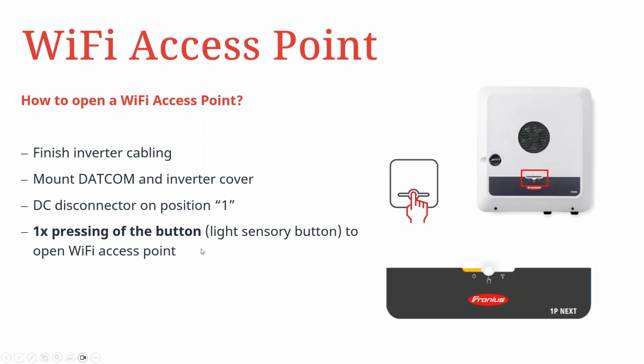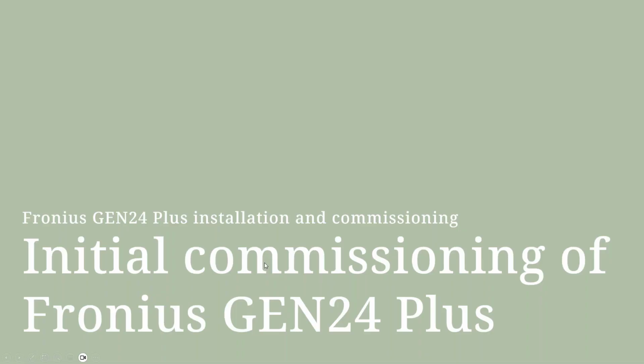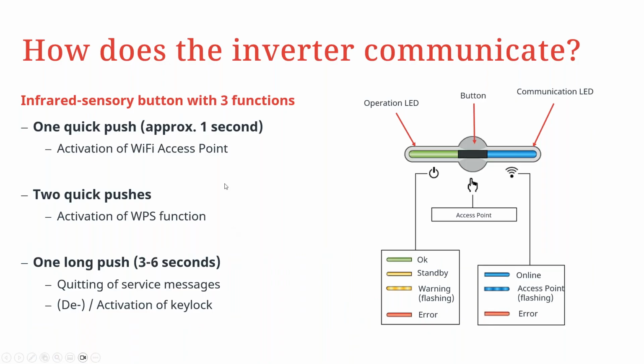This is triggered by simply pressing the touch-sensitive button right between the status LEDs, as you can see. Once you press the touch-sensitive button once, in approximately a second, you open the Wi-Fi access point, which will be indicated by the blinking of the blue LED. We're going to discuss more on that in the coming slides. So going forward to the installation and commissioning of the GEN24 Plus, we now continue from where we stopped in terms of having access to the inverter.